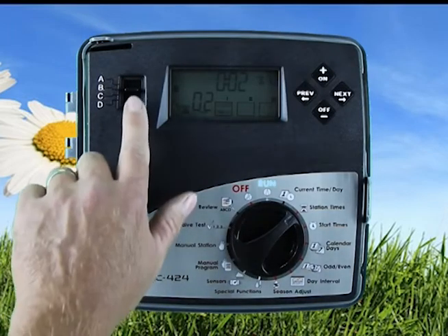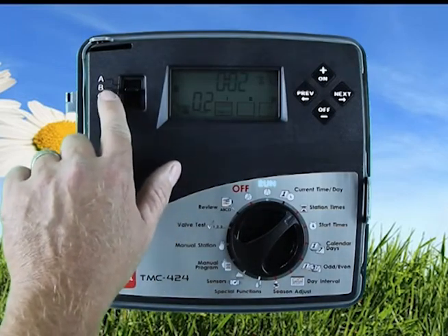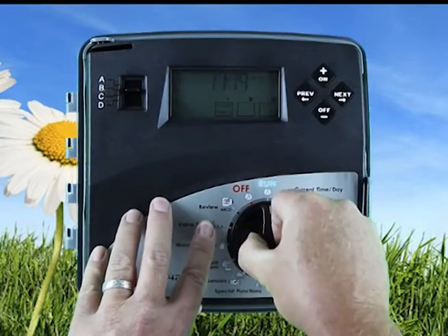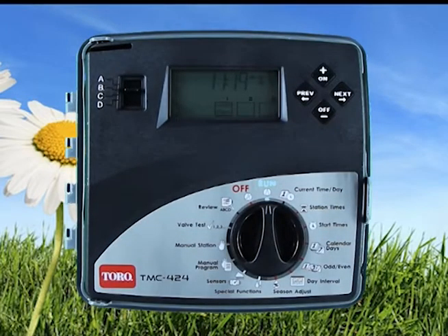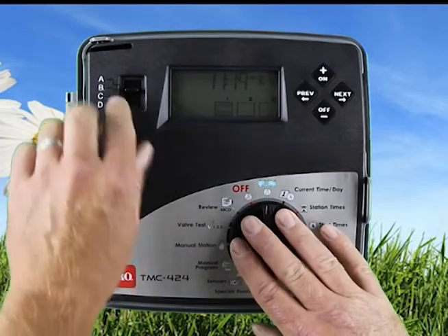Now, just because the dial or this selector is in the B mode and I come back to run, it doesn't mean it's just going to do B. No, I have a start time on A. In fact, I have 2 start times on A and a third start time on B right now. It will run A twice and then it will do a B cycle. This over here is only for programming.